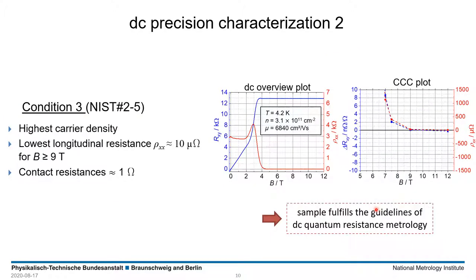The third condition was at an even higher carrier density, resulting in R_XX values around 10 µΩ starting at 9 tesla. At these flux densities, the device fulfills the requirements of the guidelines of DC quantum resistance metrology, and these conditions are also used for the AC measurements that follow in the next slides.